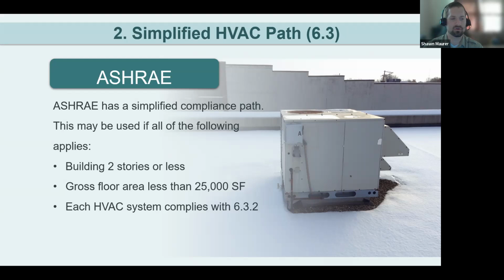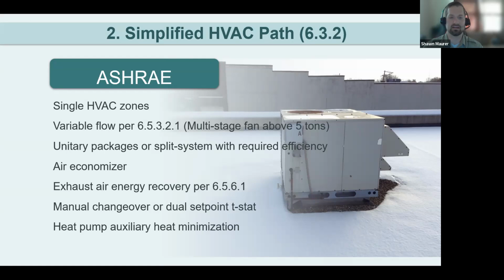But as we noted, this is for small buildings, 2 stories or less. Gross floor area has to be less than 25,000 square feet. And then there are specific compliance requirements detailed in the following section. It's 2 pages of compliance checks for the system as compared to the 70 pages for the full HVAC compliance to try to work your way through. So it's a nice addition that ASHRAE has put in to simplify that reference process when looking up the code requirements. Typically there are going to be single zone HVAC systems. They can have variable flow or multi-stage fan flow if they're above 5 tons in size.